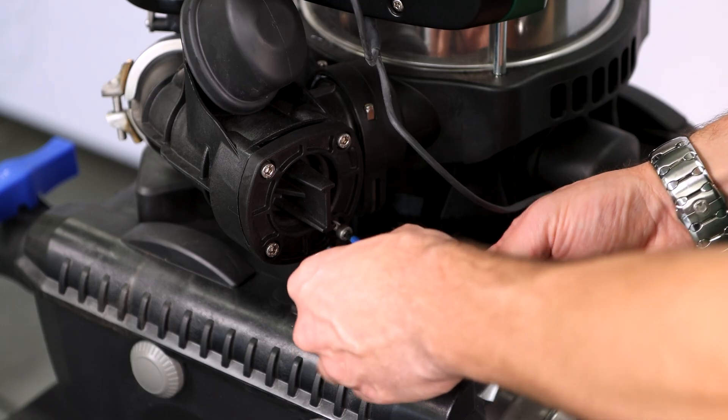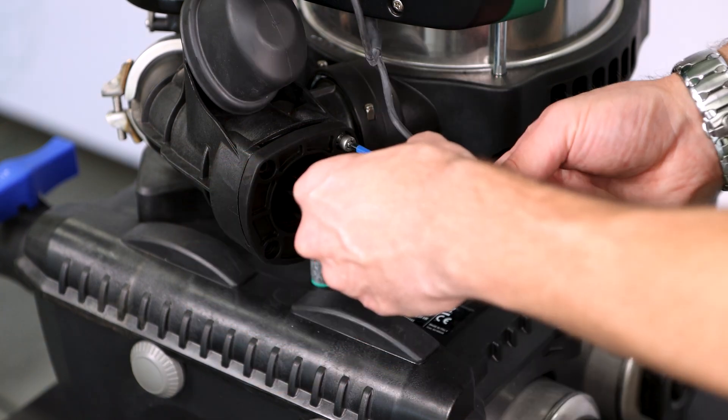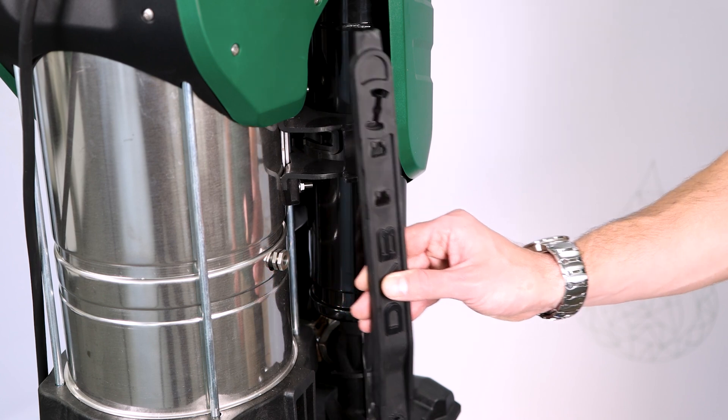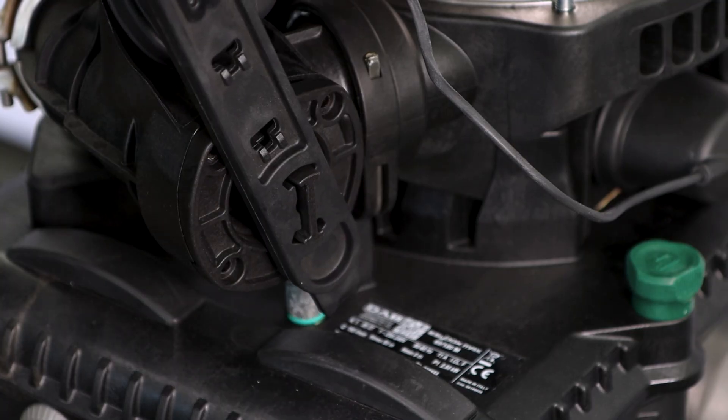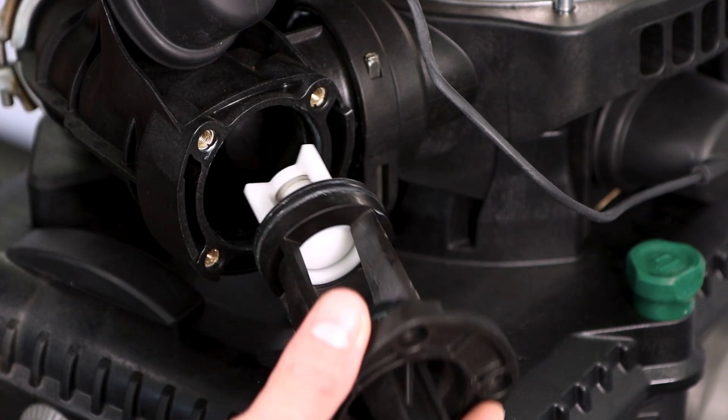A huge advantage of e.sybox Max is that the no-return valve is easily accessible and easily removable. Four screws to be undone — one, two, three, and four. Grab the tool sitting here behind the pump, a quick rotation, and the valve is popped out.